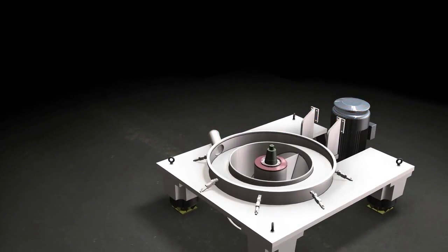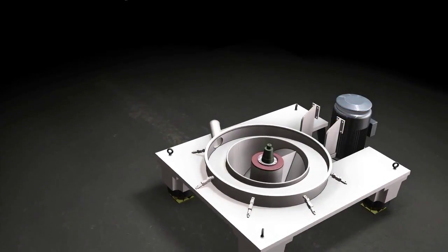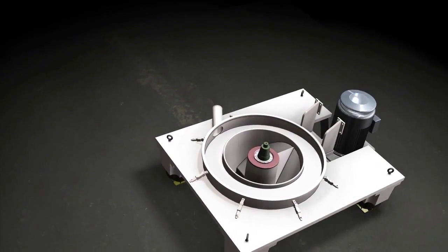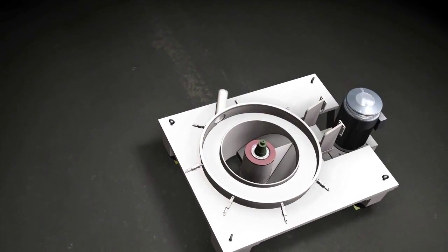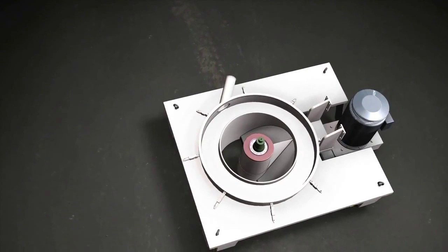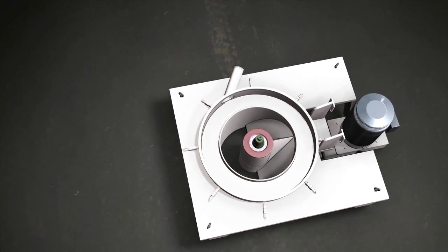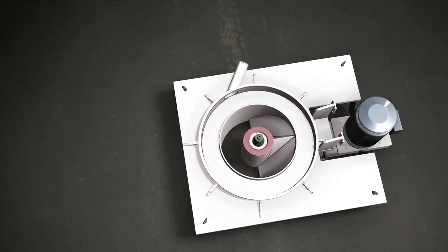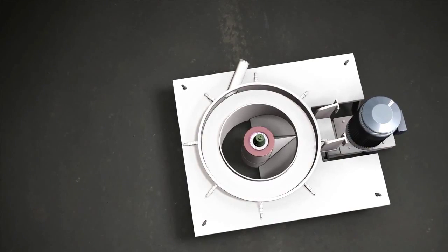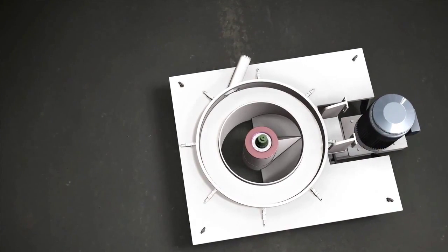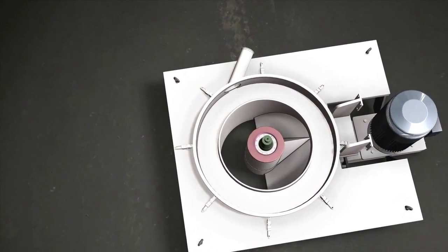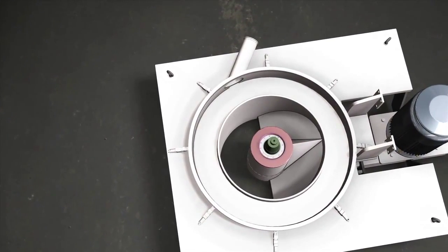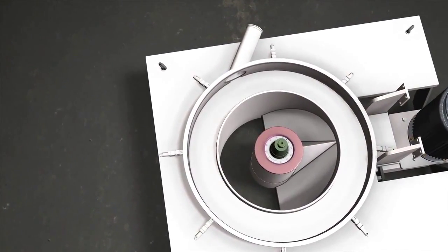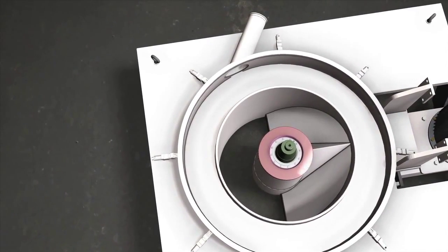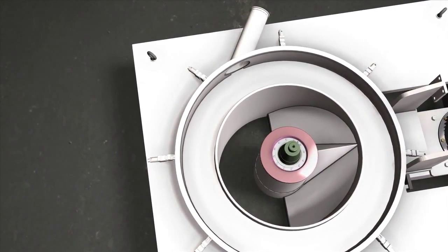The QuadraClean filtering centrifuge features a discharge system designed to promote easy and complete recovery of the high-value solids. The discharge system employs a steep vertical inclined discharge chute and works in conjunction with the proven and reliable Western States monocut discharger. The monocut discharger uses a full-length plow blade with replaceable cutting tip to remove the product in a single inward motion, which is positioned to promote the flow of the solids into the open area of the chute during the discharge cycle.